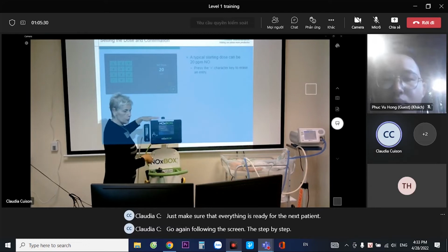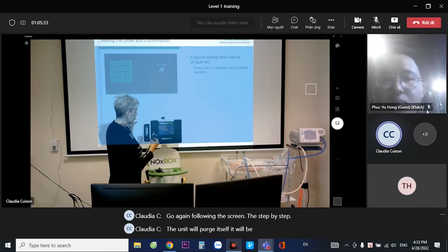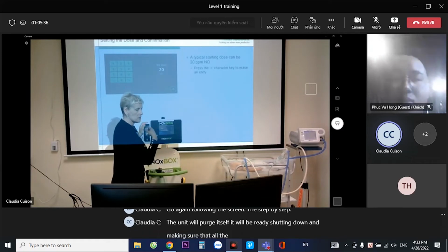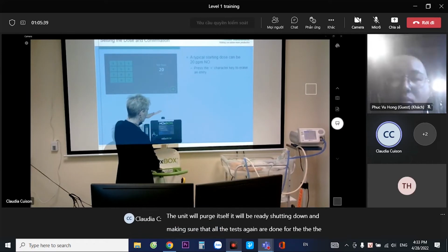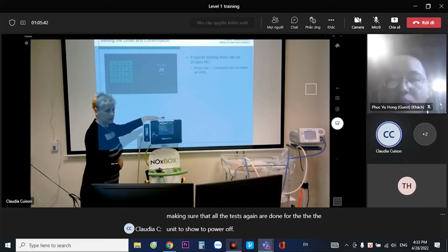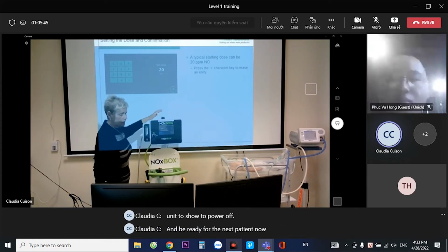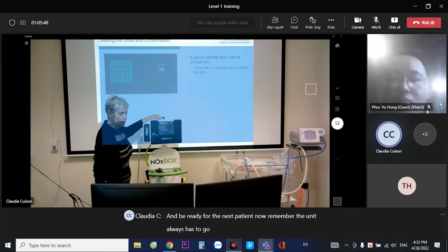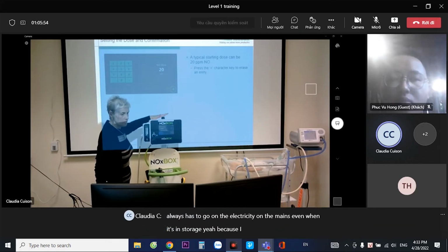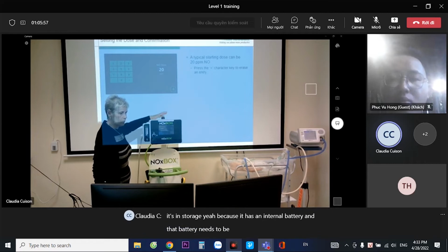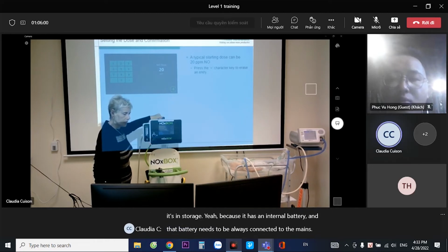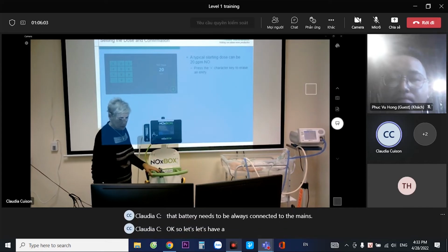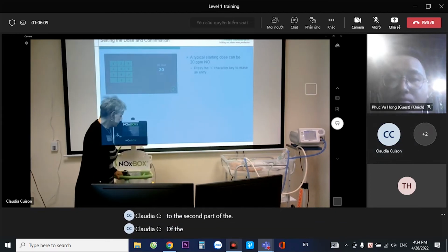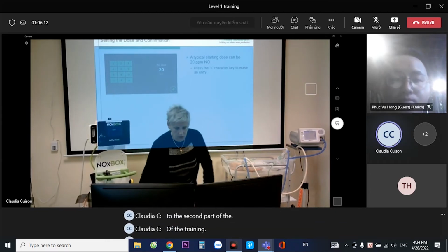So again, following the screen, the step by step, the unit will purge itself. It will be ready, shutting down and making sure that all the tests again are done for the unit to power off and be ready for the next patient. Now remember, the unit always has to go on the electricity, on the mains, even when it's in storage, yeah, because it has an internal battery and that battery needs to be always connected to the mains. Okay, so let's have a little 15 minutes pause before we go to the second part of the training.